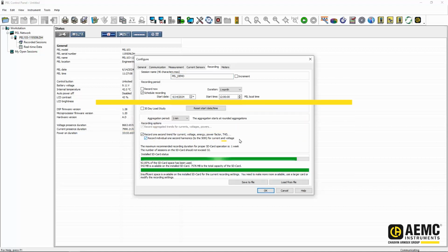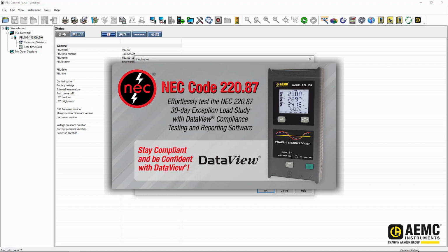A new feature to the PEL control panel is the 30-day load study selection. When I click this, it automatically configures my aggregation period as well as selects the next hour for the start time of my recording, as well as sets the duration to 1 month. This function could be very helpful for those of you performing load studies according to the NEC 220.87 requirements.